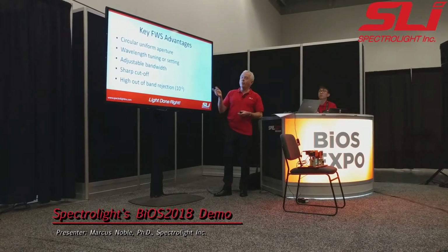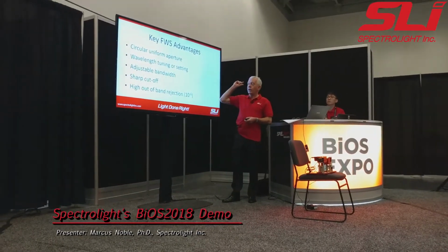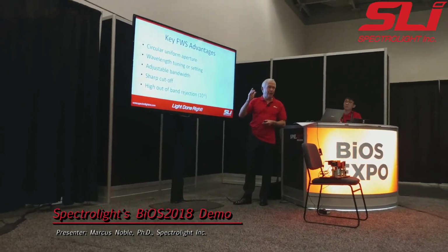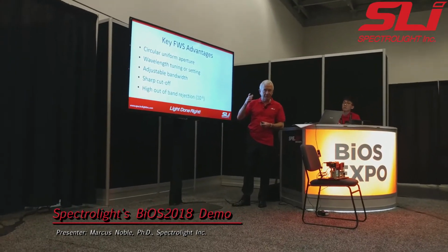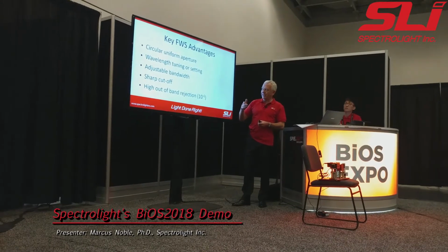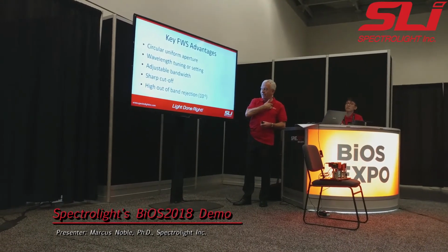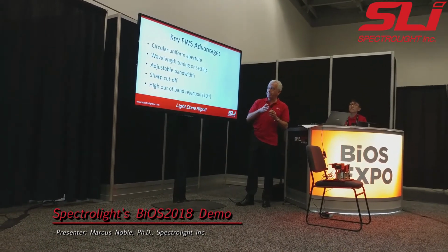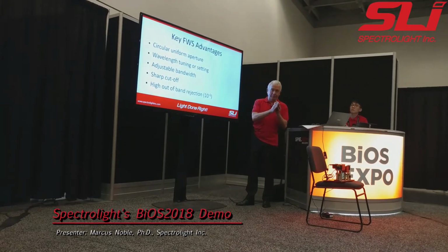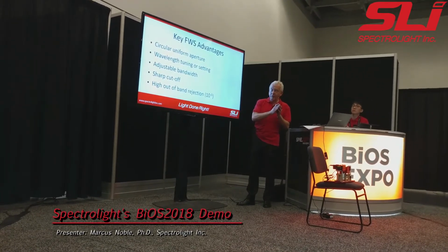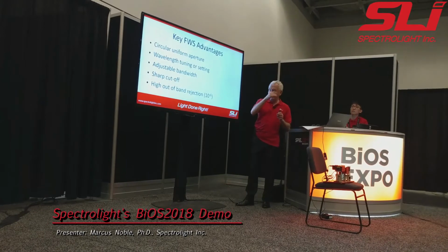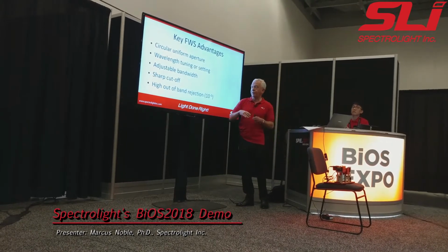So to recap the advantages, we've got a circular uniform aperture. I know I keep emphasizing that, but whenever people think of any kind of spectral instrumentation, I'm saying that we're covering spectroscopists, you think of some device with a slit or a pinhole that defines the wavelength. The wavelength's defined here internally, so the entire aperture is uniform.